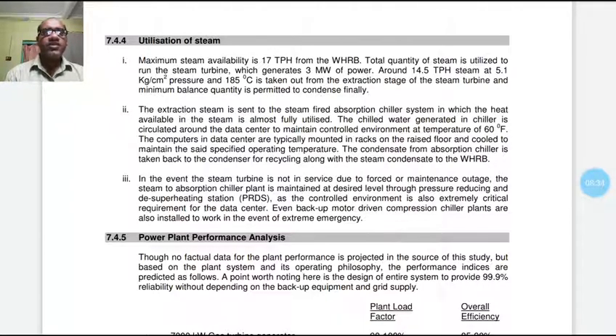In the event the steam turbine is not in service due to forced or maintenance outage, the steam to the absorption chiller plant is maintained at the desired level through a pressure reducing and desuperheating station. As the controlled environment is also an extremely critical requirement for the data center, even backup motor driven compression chiller plants are installed to work in the event of extreme emergency.